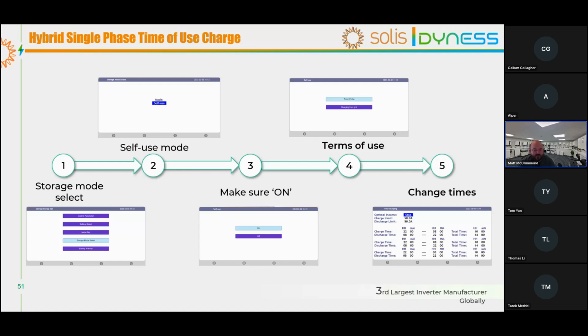If you wanted to change this time of use on the inverter itself, you can do it by going through the menu structure. So going into the work mode, time of use, selecting storage mode, select on, and then it will take you to the time of use windows for you to set up. Most of the time people do it through Solis Cloud or through the app, so they don't actually have to access the inverter at all. But if a customer for whatever reason wanted to do that, they can also do it on the actual unit.